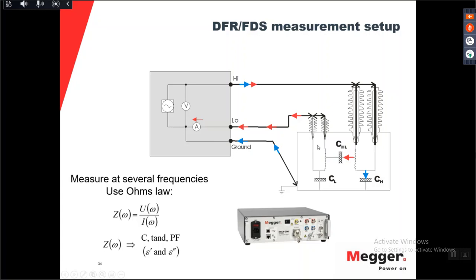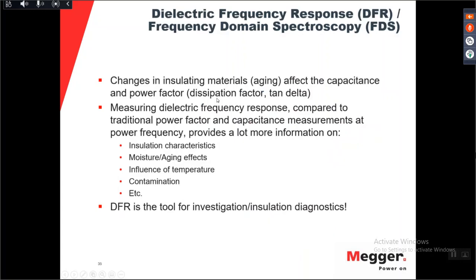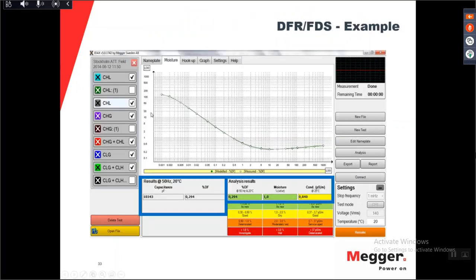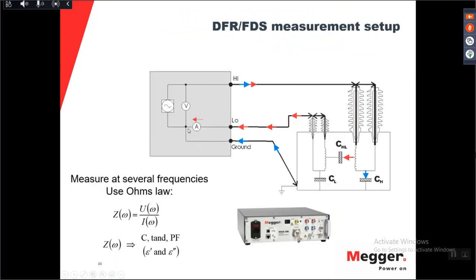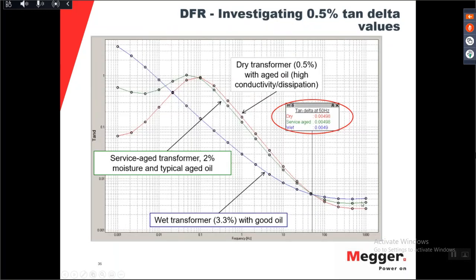So what is the benefit of doing it over a wide frequency range? Because the insulation materials will change due to the different aging effects, both the capacitance as well as the power factor. And giving it a frequency response, you can separate whether it comes from the moisture, or if it's a temperature effect, or if it's a bad oil, etc. If I give you an example, you remember this curve that you measured? What does this mean? If I give you 3 different curves, you can see I get 1, 2, and 3. What is the difference between these 3 measured curves?